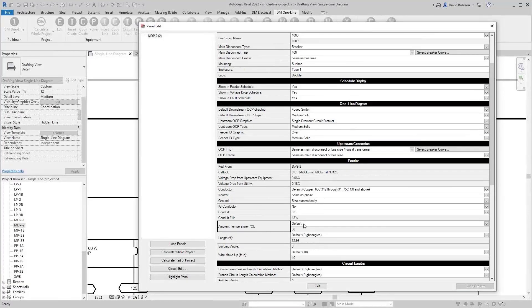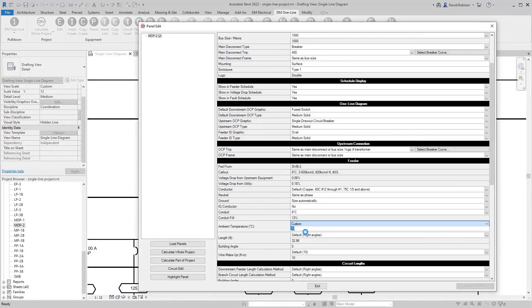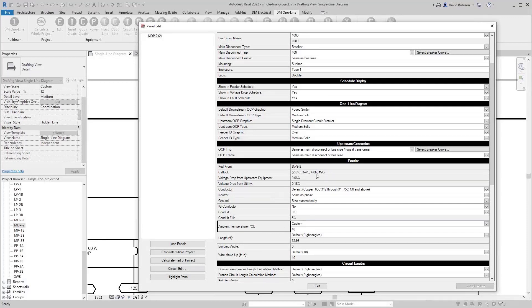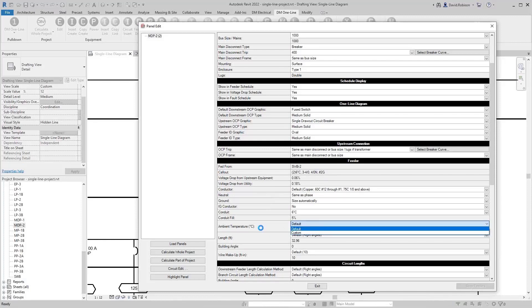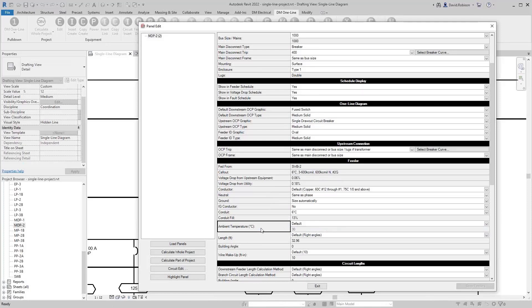We also have the ambient temperature setting, used for derating. By default it's 30 degrees. If you increase that temperature, we derate the wire — for example, going from 600 kcmil to two runs of 4/0. The NEC has gone through revisions on how to treat temperature over a roof, so you'll need to look at the current NEC for your area to determine any roof adjustments, and manually type in the corresponding ambient temperature.